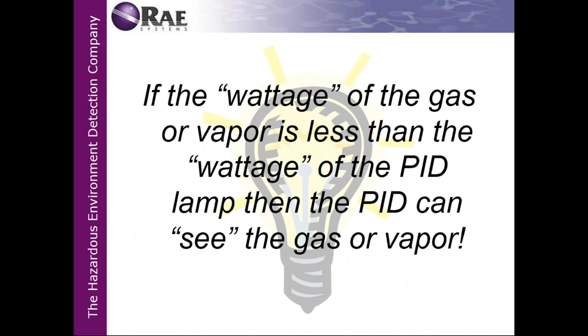You have to look at the lamps, the 9.8, the 10.6, and the 11.7, as wattage of gas lamps. If the wattage of the gas or vapor is less than the wattage of the PID lamp, then the PID can see the gas or vapor. Again, if we had a 9.8 lamp inside that monitor, it would be able to recognize a 9.71 eV. Okay?